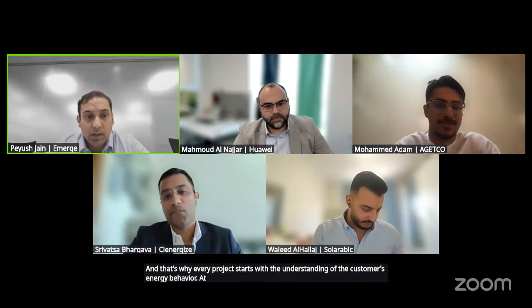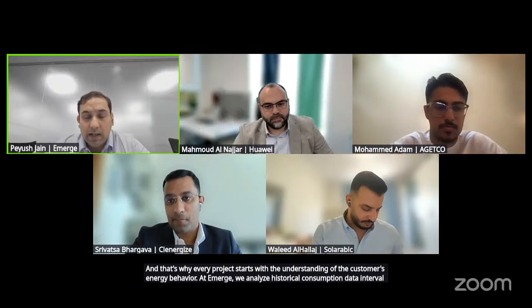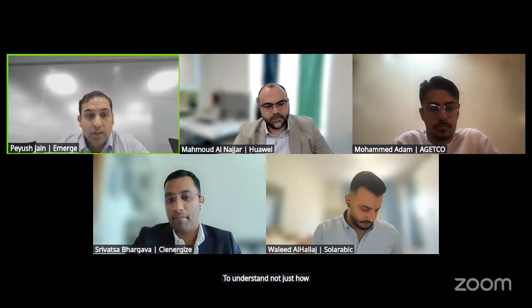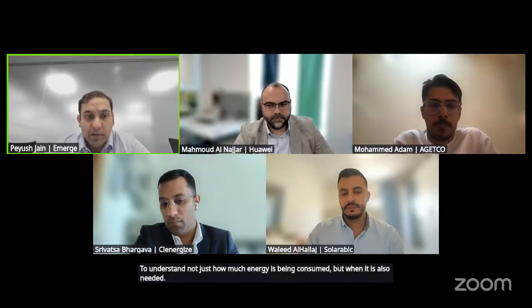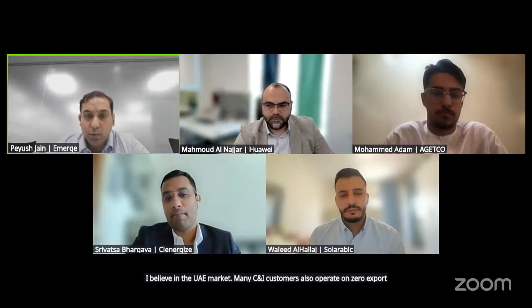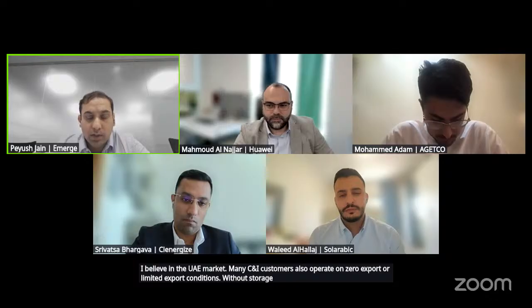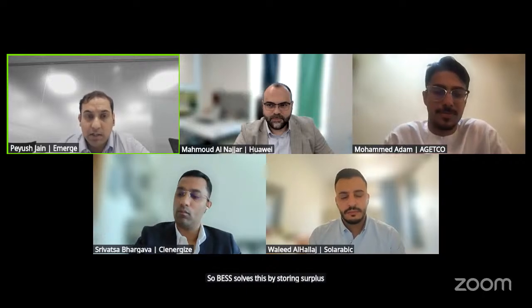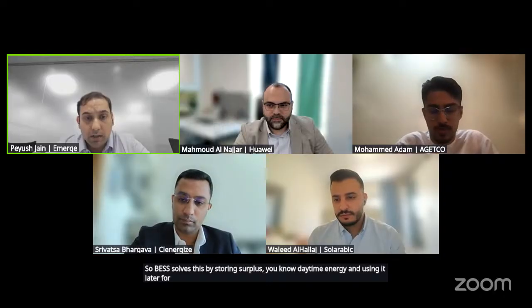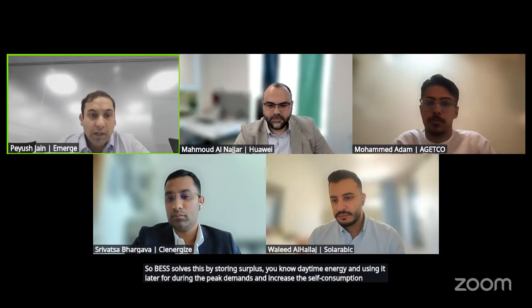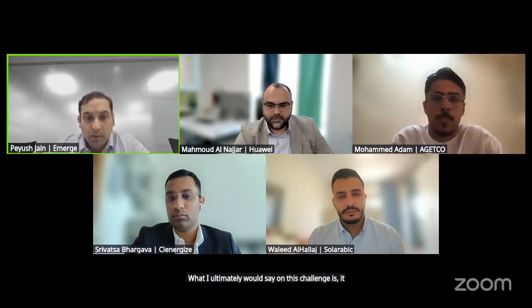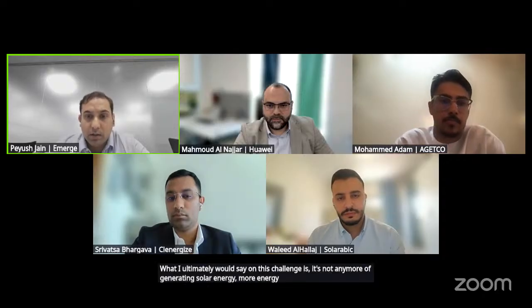At Emerge, we analyze historical consumption data, interval meter data, and ideally an 8760-hour load profile to understand not just how much energy is being consumed, but when it is also needed. I believe in the UAE market, many C&I customers also operate on zero export or limited export conditions. Without storage, excess solar energy is simply curtailed. So BESS solves this by storing surplus daytime energy and using it later during the peak demands and increasing the self-consumption. What I would ultimately say on this challenge is it's no longer about generating more solar energy, but about ensuring every unit of solar energy is used effectively.